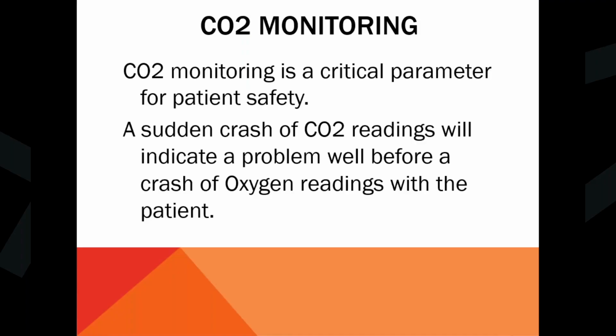Now, CO2 monitoring is a really critical part of the anesthesia machine, even though it's on the patient monitor, not on the machine itself. Back in the day, when I first got into biomed, we had these things called capnographs. Capnographs were on the anesthesia machines, and they'd also use them up on the floors. Patients that had been on either sedation or heavy narcotics were then put on a CO2 monitor to keep track of them. And this was normally up on the floor.